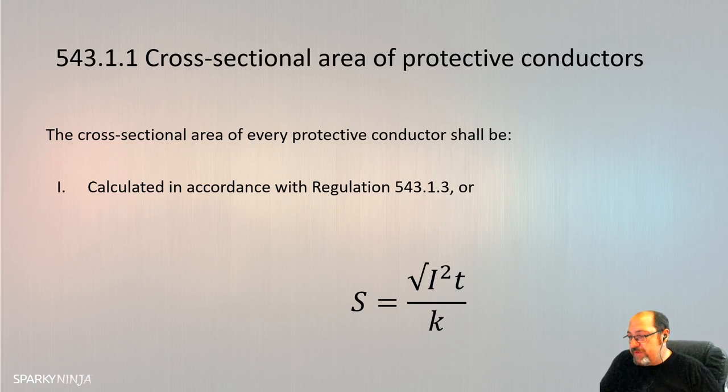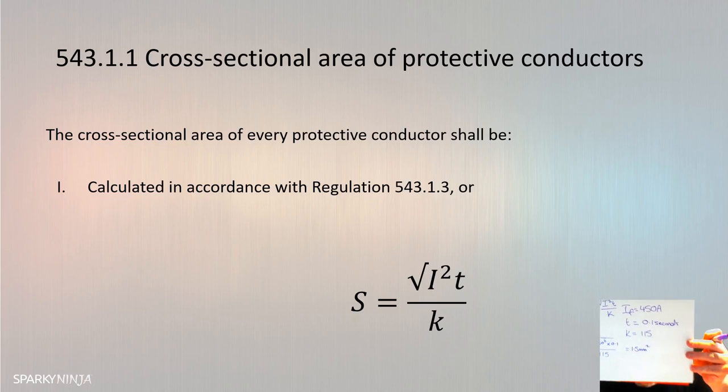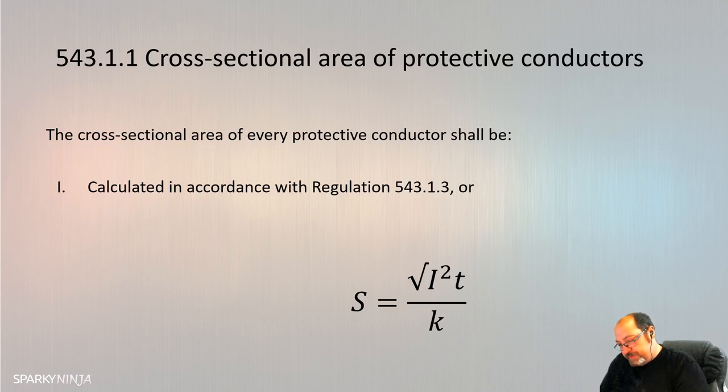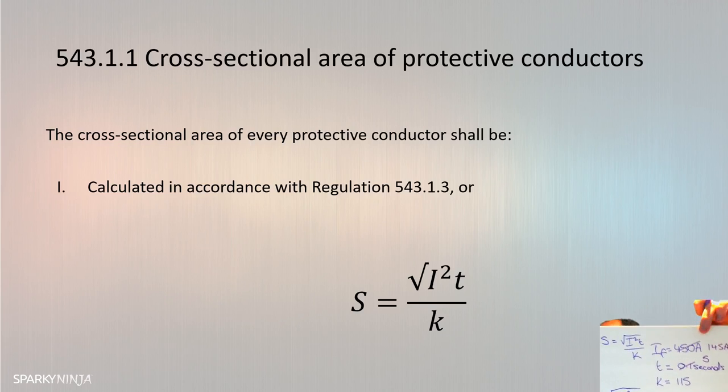And if we look at 45 amp, it's 145 amps, okay? Page 366, table or figure 3A2B, 45 amp, look at the table in the corner, 45 amp, then go along to the 5 second column, all right? Hopefully I've not lost any of you with that. So what we're going to change here, we're going to change the current to 145 and the time to 5. All right, that's what I've done there. Changed the current to 145 amp, and I've changed the time to 5 seconds.